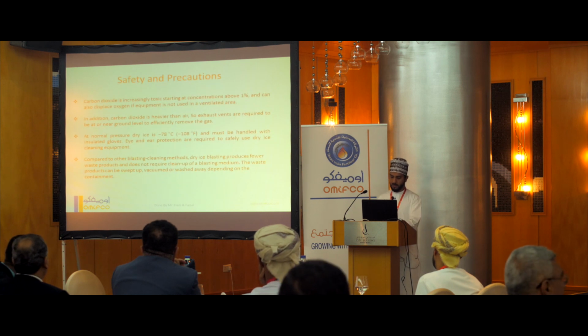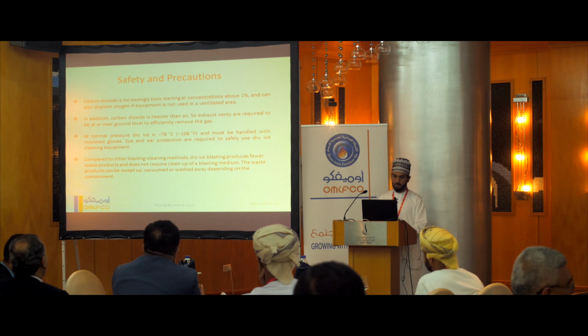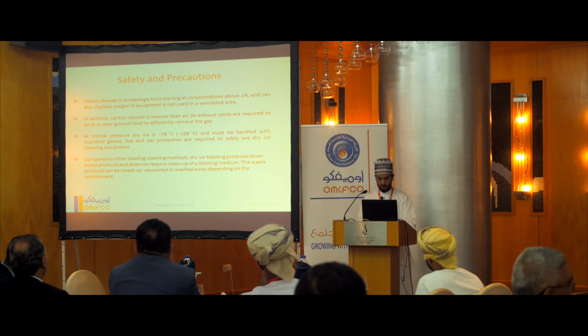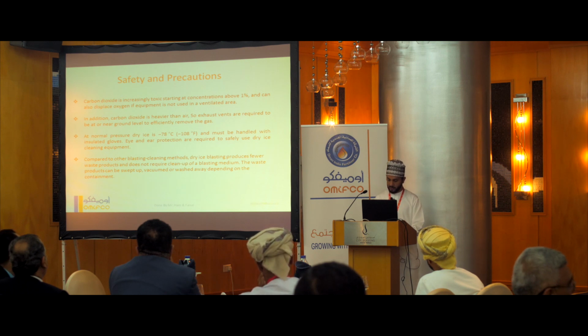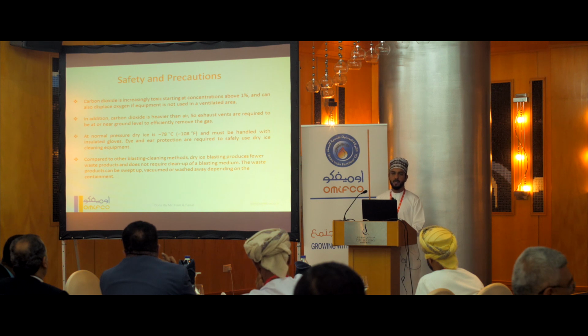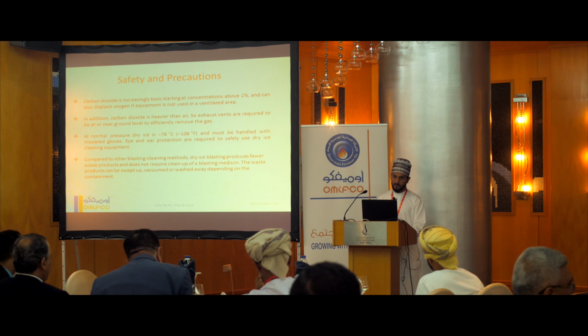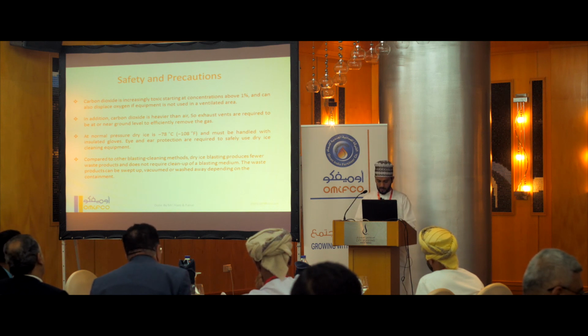On safety while dry ice cleaning is taking place: carbon dioxide is toxic at high concentrations above 1%, and can displace oxygen if the area is not ventilated. So we have to keep the ID fan running to avoid high concentrations of carbon dioxide while people are working, and keep the air refreshing, replacing the CO2. In addition, carbon dioxide is heavier than air, so the exhaust vent is required to be near ground level to remove the gas.